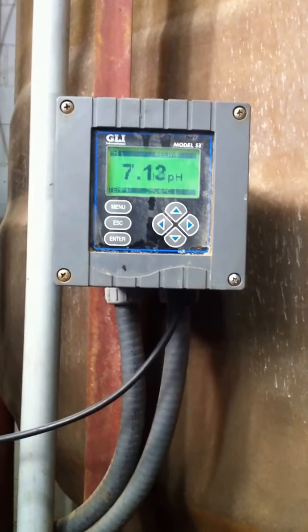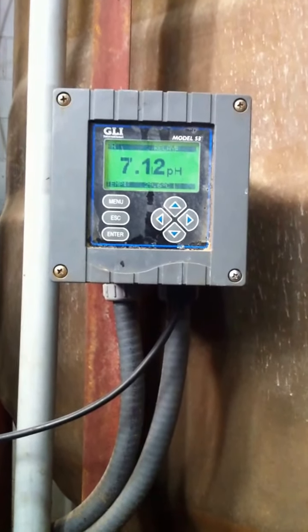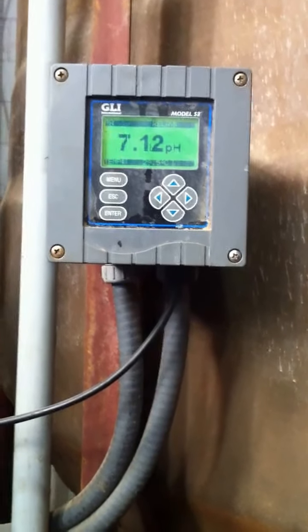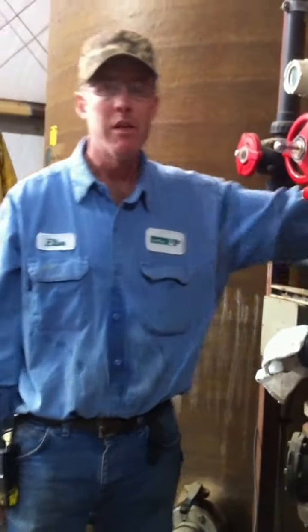Looks like it's going to stabilize around a 7.12. And like I said, that's the calibration process for a GLI Model 53 pH probe on a 2-point buffer. It's good.